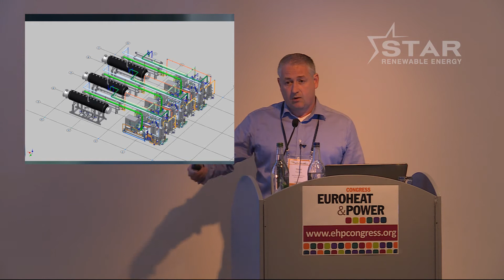Not the best photograph, but the point of this one is we're actually even recovering the waste heat from the electric motors, which is around about 3%, and we feed it back into the system. So you will have heard the stereotype of the Scots being very tight. We're also very tight with kilowatt hours as well as pounds. And this is the good number for us. We're getting an efficiency, what we call a coefficient of performance, of over 3. So for every 1 unit of electricity that we consume, we're getting 3 units of heat. And that's quite a significant ratio, far higher than they were expecting.